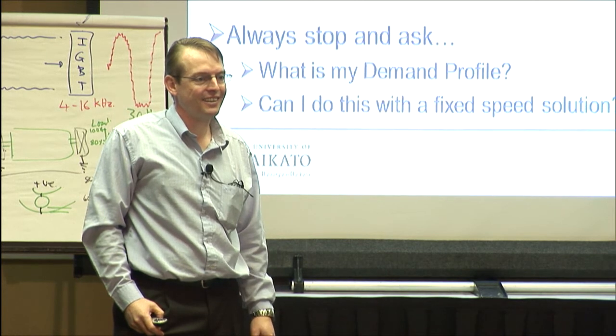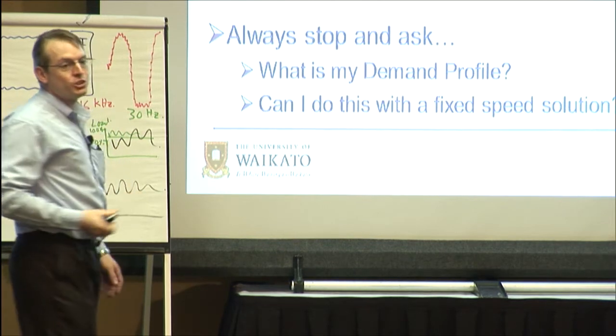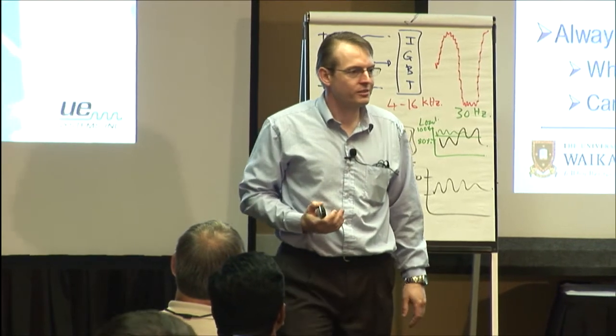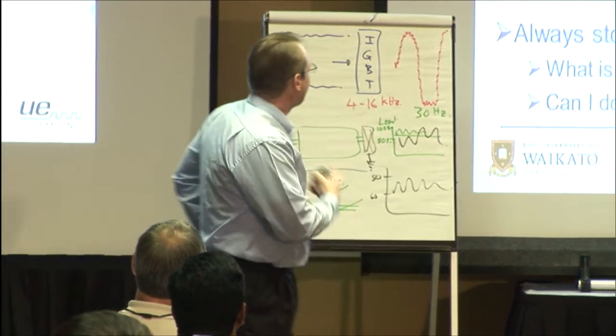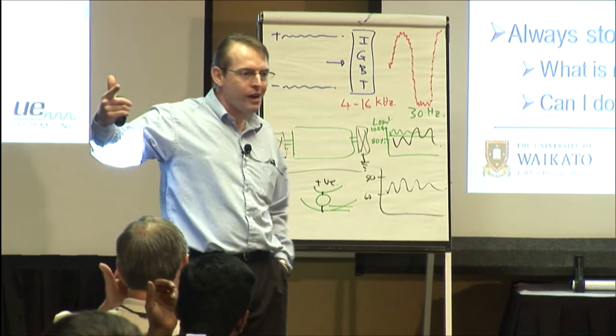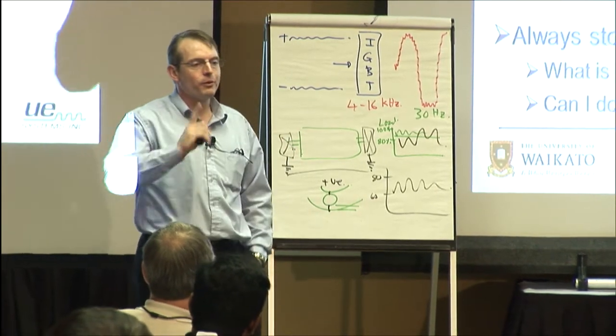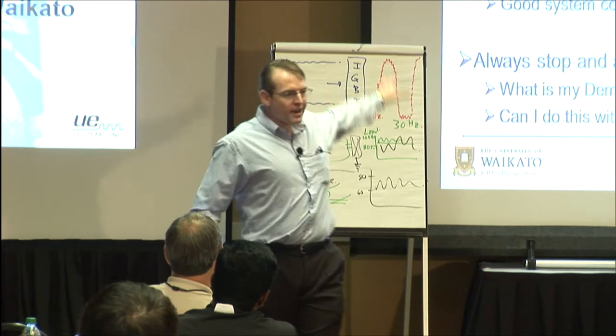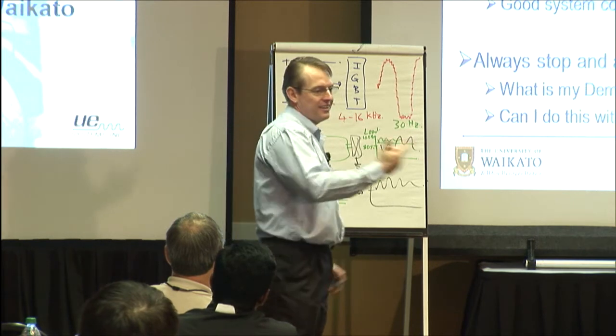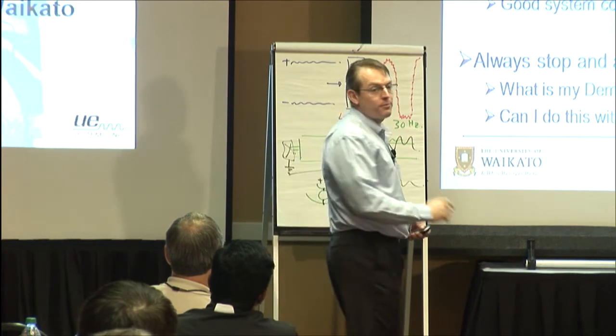Right? Okay. So a little take-home message, guys. A job done right is a job done once. And it applies to this more than ever. Okay? VSDs can be a powerful solution if you've got the correct installation, good harmonic filters, correct bearing management, and good system control. Okay? But remember, key point, before you worry about any of that, what's my demand profile? Do I even need to add a VSD? Okay, do I have any questions from any of you before we move on?